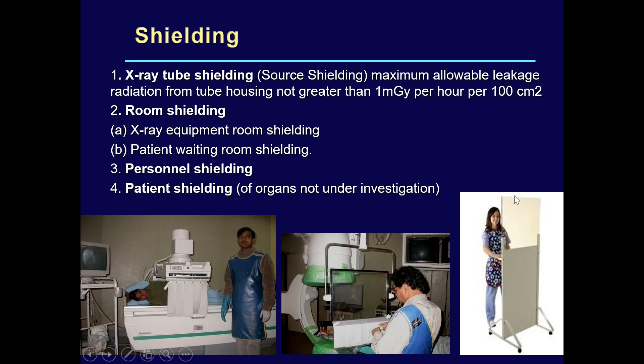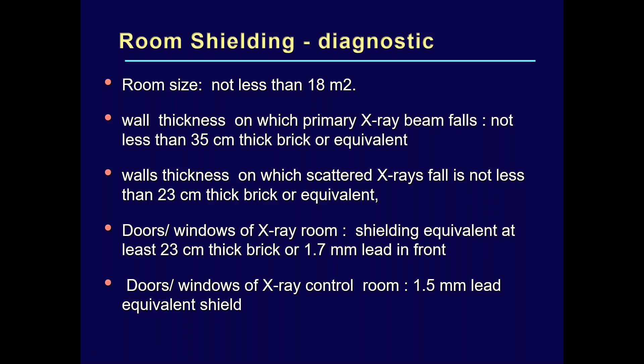Now, for an ideal X-ray unit, the room size should be at least 18 square meters, and the wall should be made of brick, 35 centimeters, and there should not be any windows where the radiation can scatter and someone sitting adjacent to the X-ray installation gets the radiation dose. Plus the doors and the windows are always lead lined. They are 1.7 millimeter lead lined on the door for all X-ray installations.